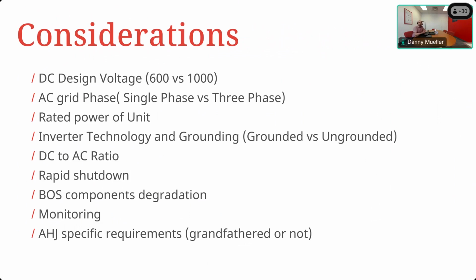Most of this stuff is quite easy to address. Even something like DC to AC ratio - discussions can be had with manufacturers like Fronius on how to best address that, either through getting authorization to oversize to 2-to-1, or by derating inverters so they're able to handle the additional oversizing. So all that stuff can be addressed. Most of it is pretty standard, but it's important to point them out as things to check before installing a new inverter.